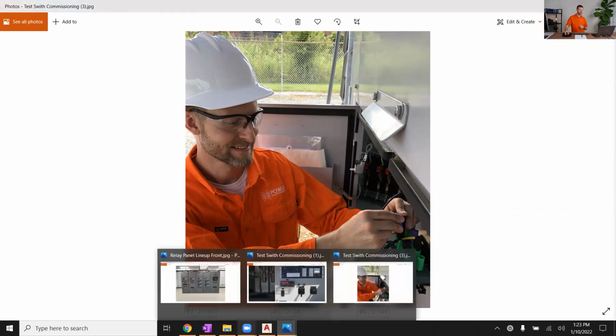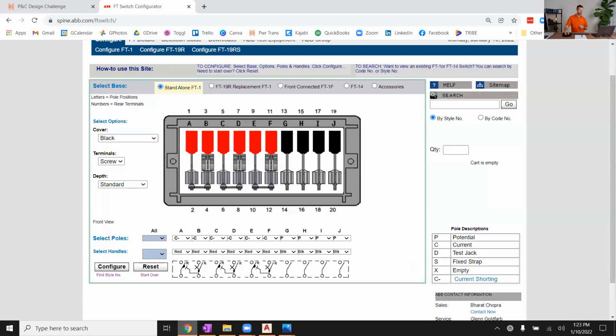The convention is that the top of the test switch, the odd number terminals, are wired to the back of the relay to your IA, IB, IC, in and out, polarity dot and non-polarity dot signals. The 13 through 19 here would be wired to VA, VB, VC, and then you jumper them together on the back of the relay and bring back a VN, a neutral voltage. And what you do here with the currents, we talked about how it's very dangerous to have an open circuited CT secondary wiring. So these are shorting test switches.